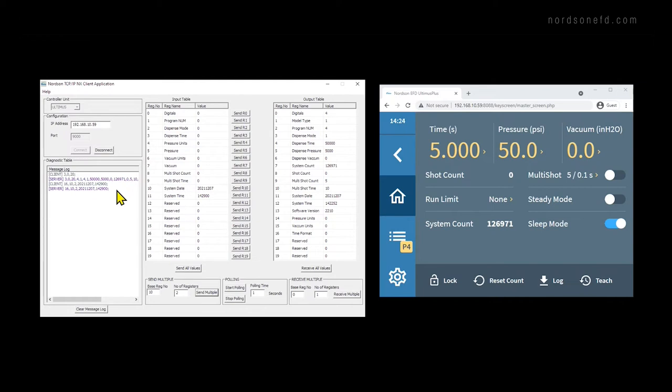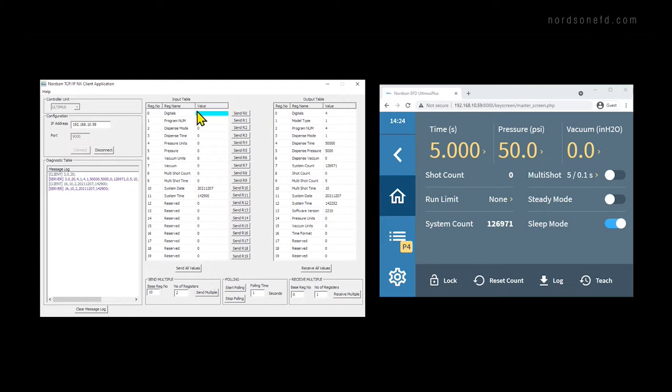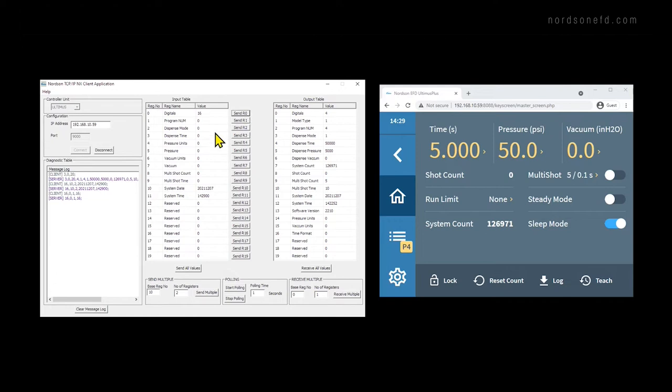To actually make this new setting take effect, we need to use the digitals register. We use the digitals register to apply all of the setting changes. The digital register is composed of different bits that represent setting changes for different features. In this case, setting the system date and time corresponds to the fourth bit, which is 16 in decimal. So I can type in the 16 here. And when I click send register 0, then the time updates. So that process did still take about two minutes. So we're now about two minutes behind. Of course, when you do this with a PLC, you'll be accurate to the second.